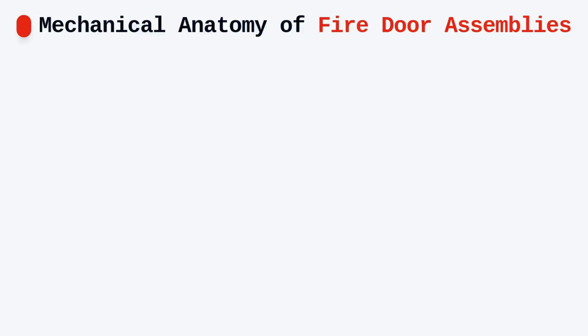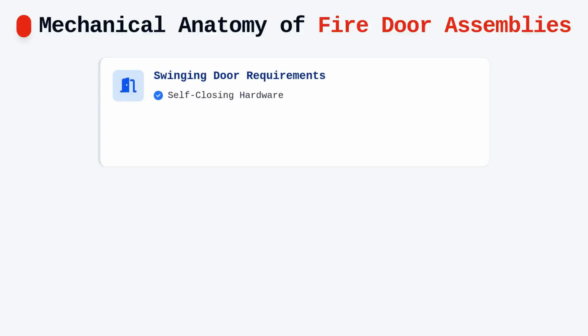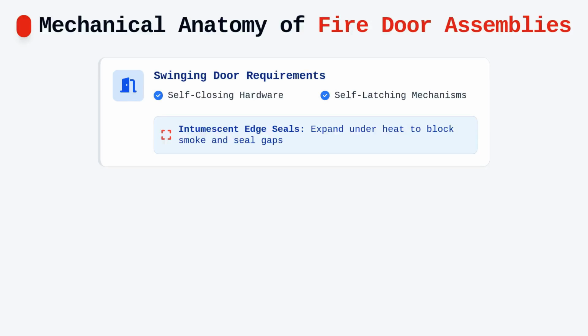The mechanical anatomy of a fire door assembly governs its ability to function automatically when a hazard is detected. Standard swinging doors must be equipped with self-closing and self-latching hardware to ensure the opening remains secured without human intervention. Intumescent edge seals play a vital role here, as they expand when exposed to high heat to close the clearance gaps around the door perimeter. These gaps are subject to strict tolerance limitations because even minor excessive clearances can allow smoke infiltration.